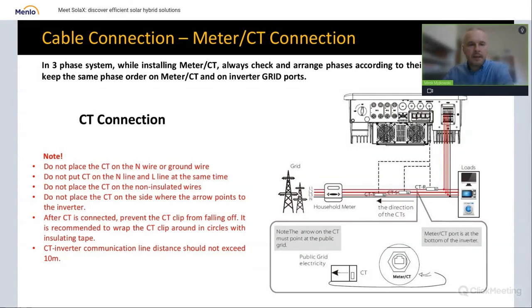And there are some rules for the CT: it should not be installed, of course, on the N wire, or on 2 wires together, or on non-insulated wires. And of course, the arrows should be pointing in the correct direction. For the standalone CT, the arrow should go to the grid. Sometimes it might happen that they will unclip themselves, so it is always a good idea to secure them with some kind of tape or something like this.